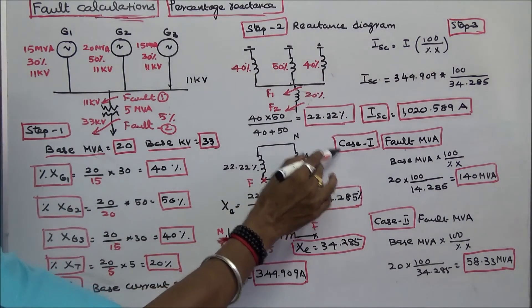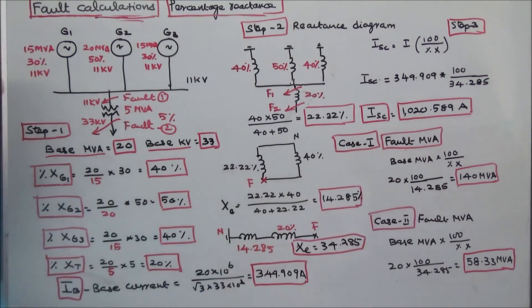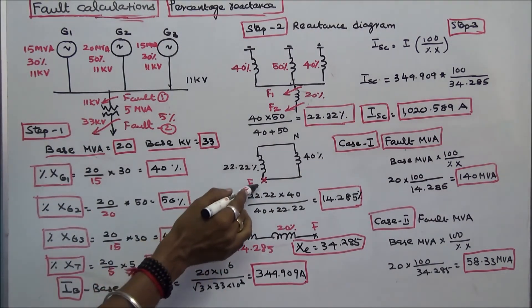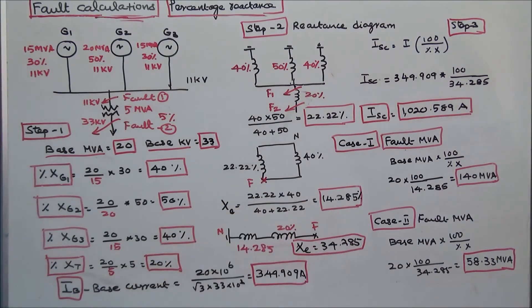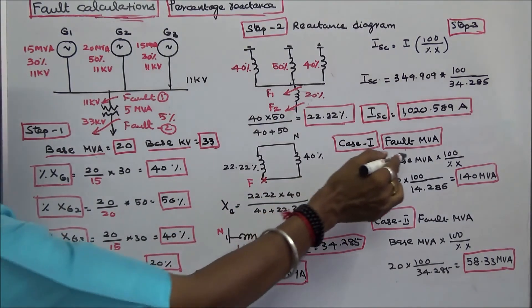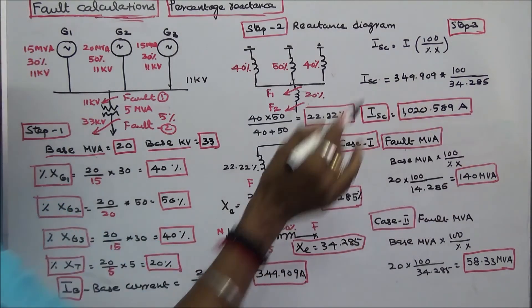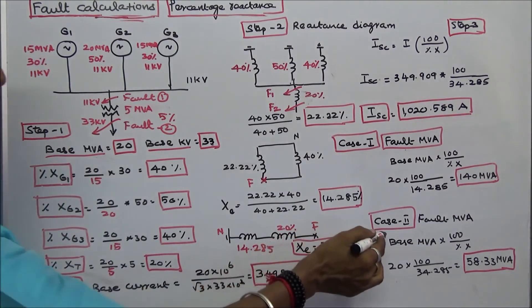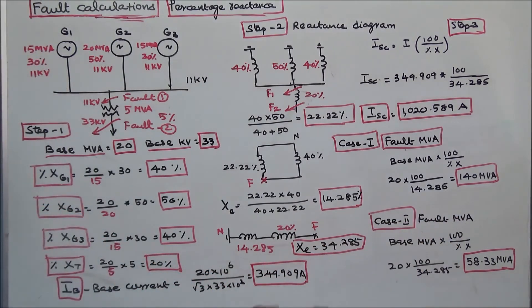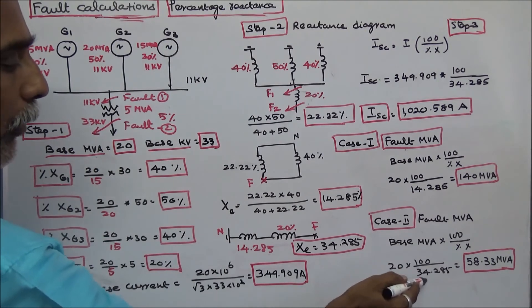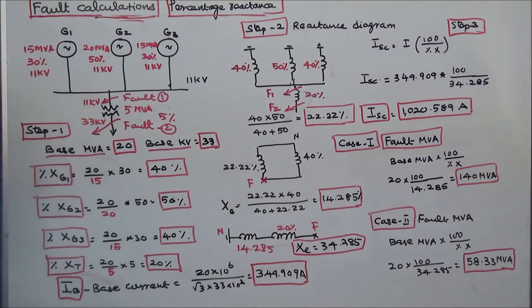Case 1: fault MVA is equal to base MVA × 100 divided by percentage X. For fault at F1, the equivalent reactance is 14.285%, so fault MVA = 20 × 100 / 14.285 = 140 MVA. Case 2: fault MVA = 20 × 100 / 34.285 = 58.33 MVA.